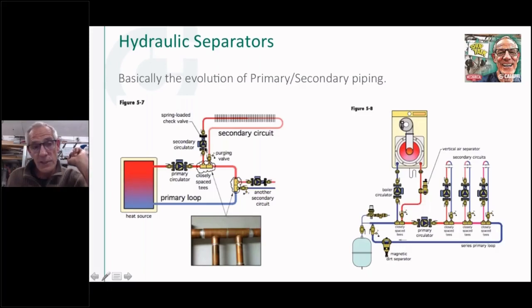So now what I can do is I can just connect whatever size circulator I need to overcome whatever load, whatever pressure drop is in this secondary circuit. So now this could be still a high head boiler with a high head pump here, and this could be a low head, this could be a high head here.